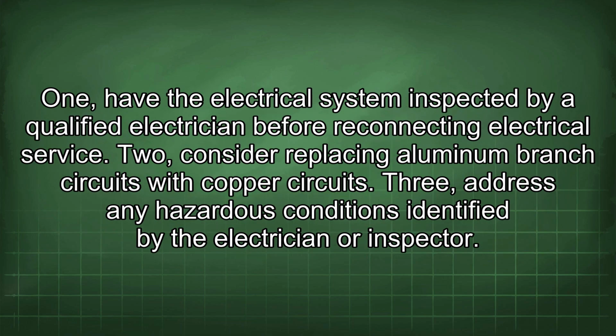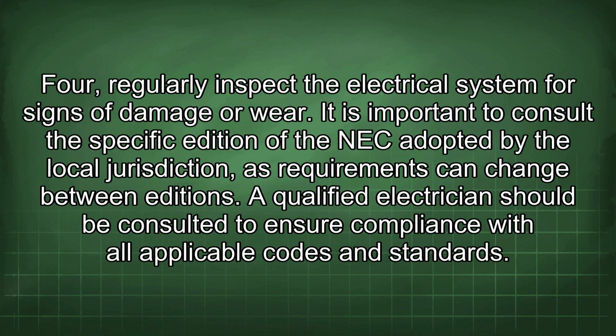To minimize the risk of electrical fires in older mobile homes, the following recommendations should be considered. 1. Have the electrical system inspected by a qualified electrician before reconnecting electrical service. 2. Consider replacing aluminum branch circuits with copper circuits. 3. Address any hazardous conditions identified by the electrician or inspector. 4. Regularly inspect the electrical system for signs of damage or wear. It is important to consult the specific edition of the NEC adopted by the local jurisdiction, as requirements can change between editions. A qualified electrician should be consulted to ensure compliance with all applicable codes and standards.